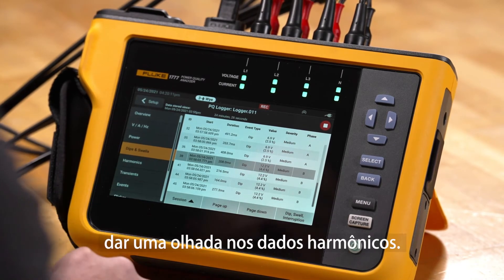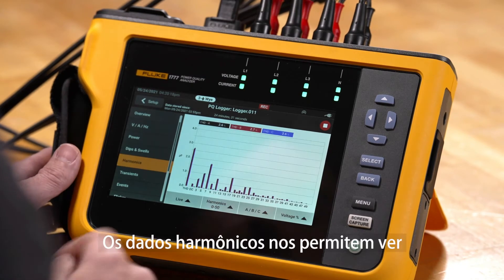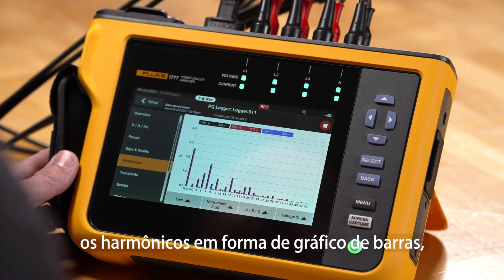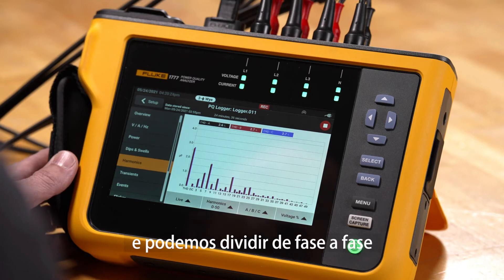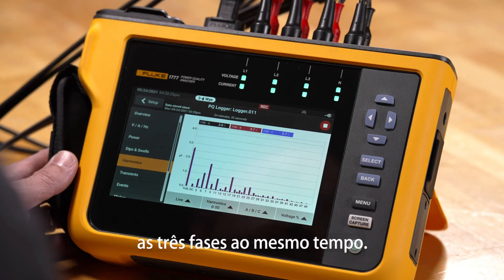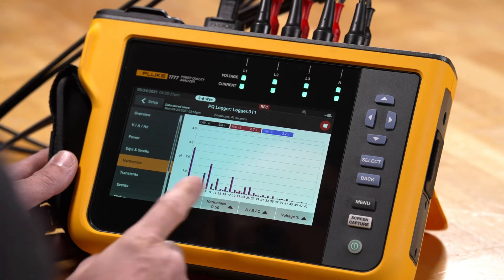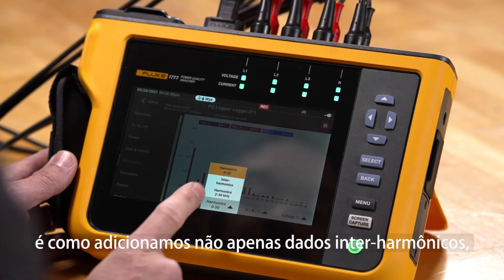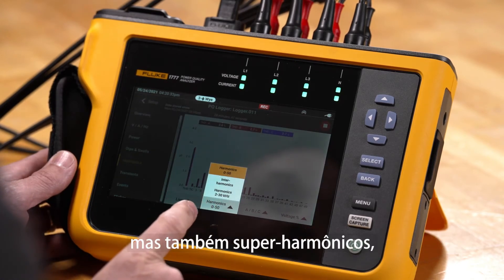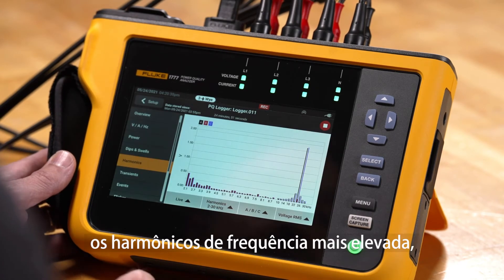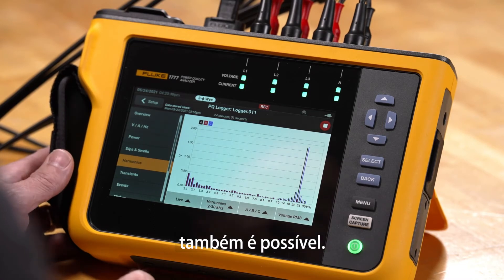We also have the ability to look at harmonic data. Harmonic data lets us view the harmonics as a bar graph, and we can break it down phase by phase or look at all three phases simultaneously. One advantage here is we've added not only interharmonic data but also supraharmonic higher frequency data, so if somebody wants to view the higher frequency harmonics, they can see those as well.